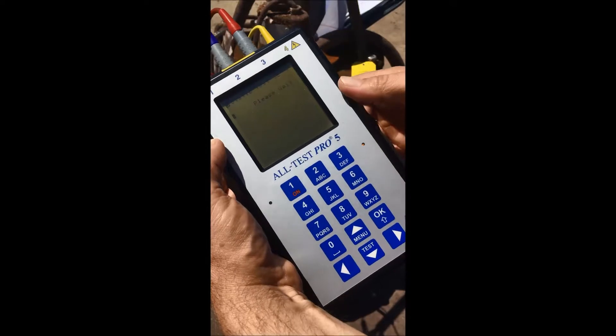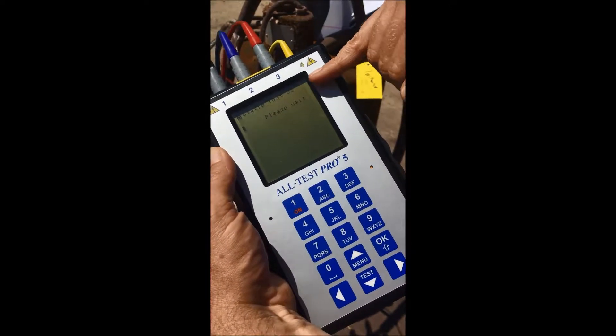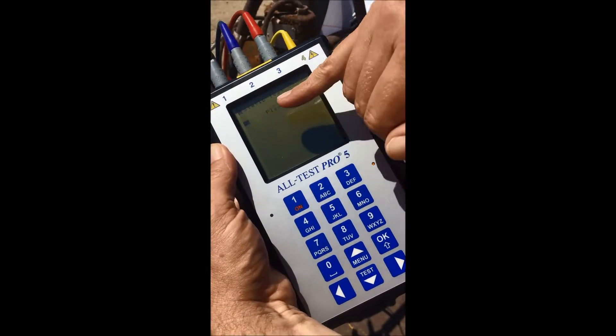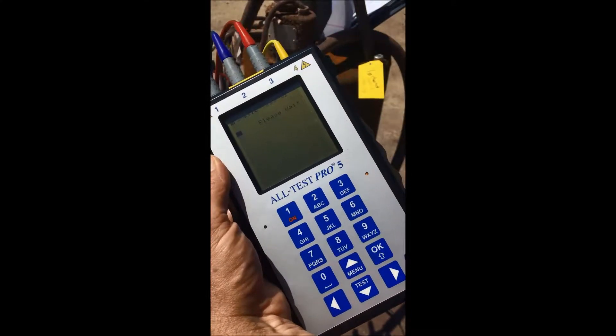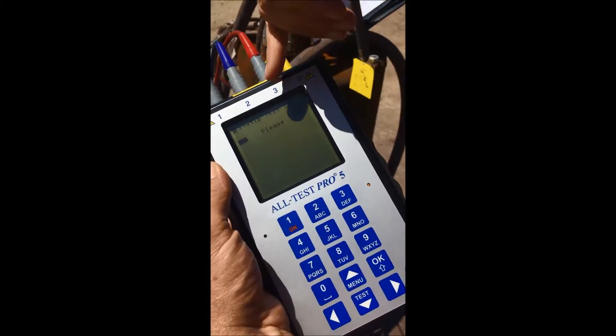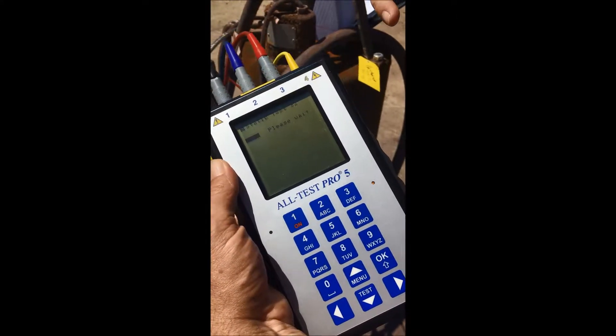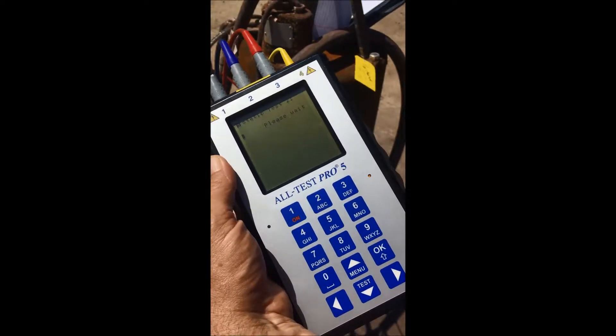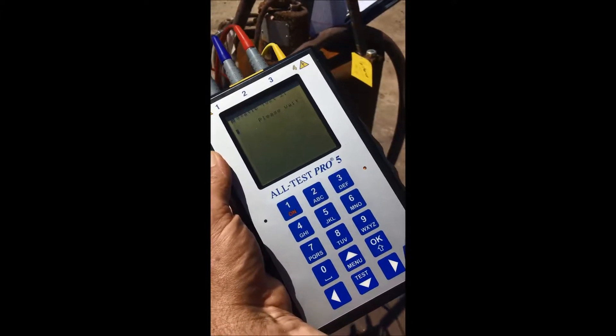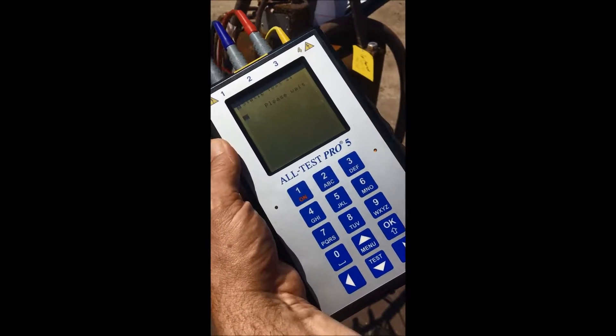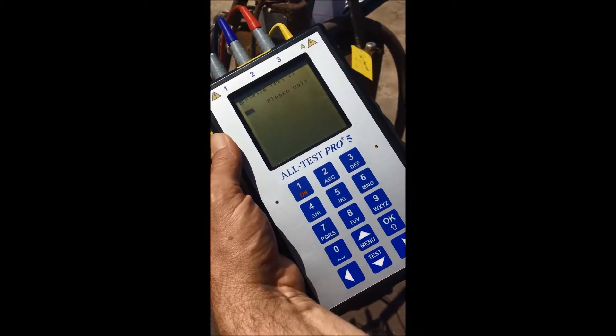So what we're doing now, it is performing a static test. We are comparing phases three to two. You'll see a status bar moving across the screen. Our signal is going through the motor. We're going to compare three to two, two to one, and one to three. What we need to find out is there any difference between the three phases. That's what this electric motor test is all about. We want to see if there's a difference between the three phases.